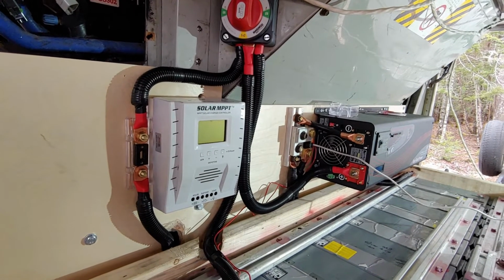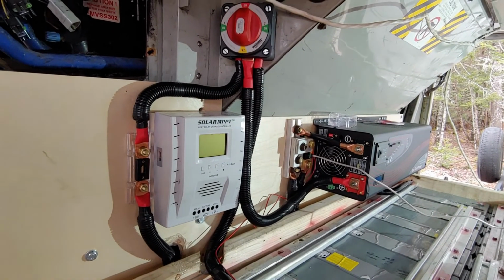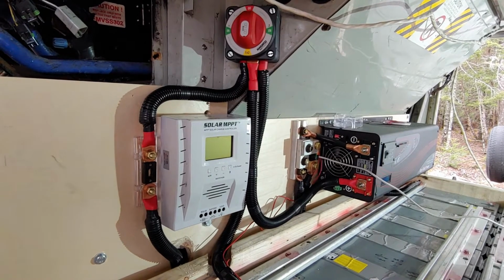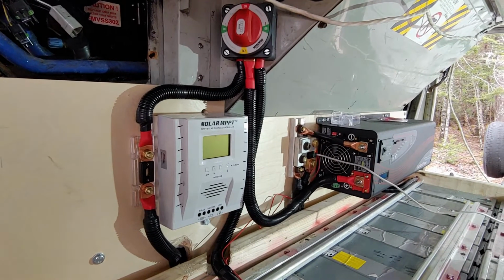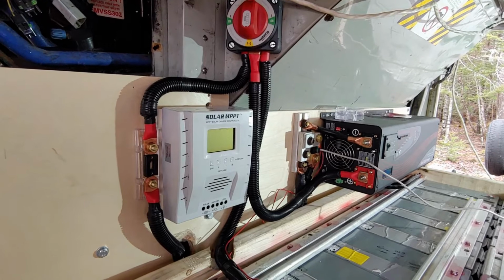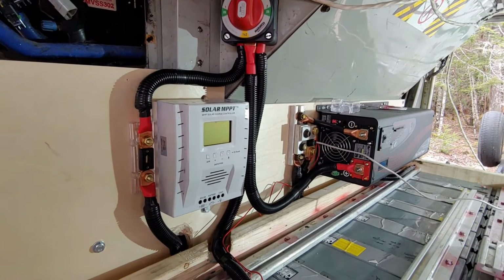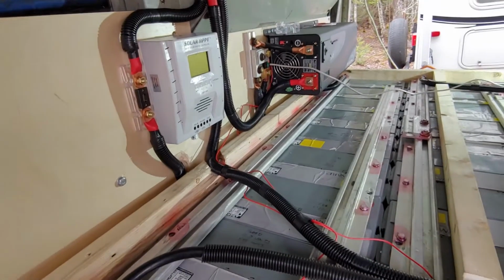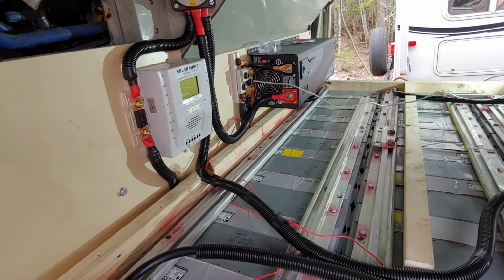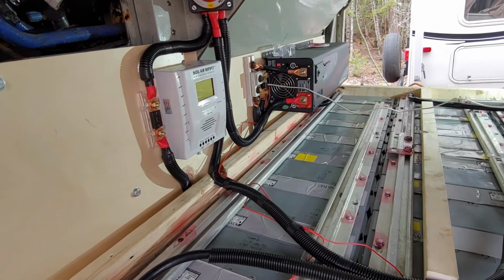I'm going to have to meter this when I turn the bus on, with a dead battery bank here, to see what kind of current I'm pulling, because this 3/0 aluminum or copper may not be enough. I think it's good for about 350. So we'll see what kind of current we're going to pull.